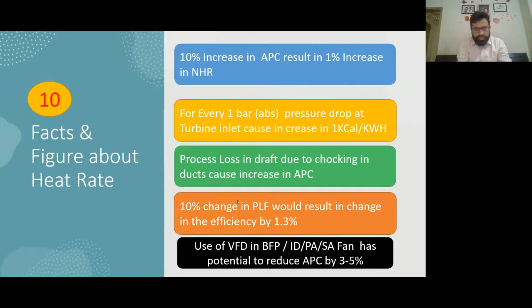A 10% increase in the power plant load factor changes the efficiency by 1.3. If we apply VFD, variable frequency drives, in BFP, now that we are at higher capacity, and we use VFDs on the turbo BFP, ID fan, PA fan, and SA fan, then we can save auxiliary power consumption by 3 to 5%. So this is a little bit of the detail I have jotted down.